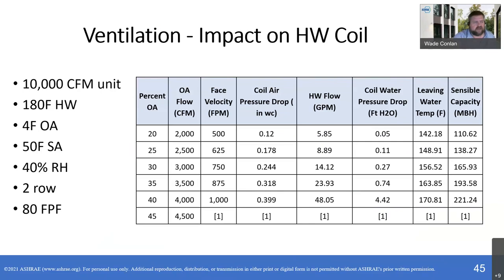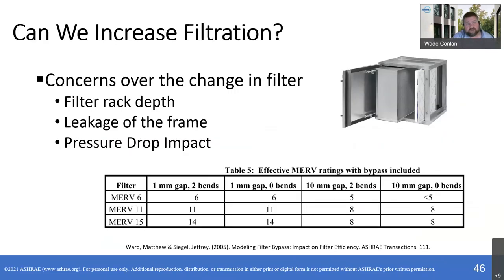So the next slide talks about filters. And we keep talking about MERV ratings and what we can get. One of the key things that goes along with this, and something I recommend to owners, is that how well these filters are installed is critical. The study done by Dr. Siegel, their modeling, he's done two or three in-situ tests that have corroborated the modeling data. It's just that the modeling report has the prettiest table to show. And you can see in that table, the MERV 15 with a 10 millimeter gap.